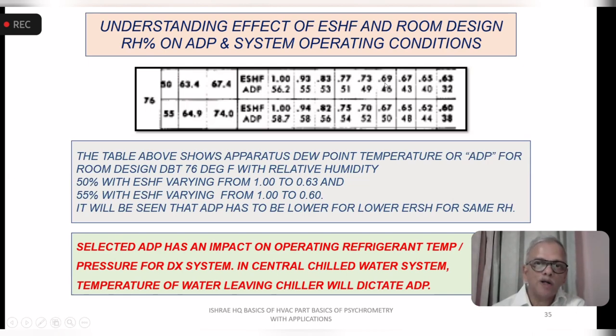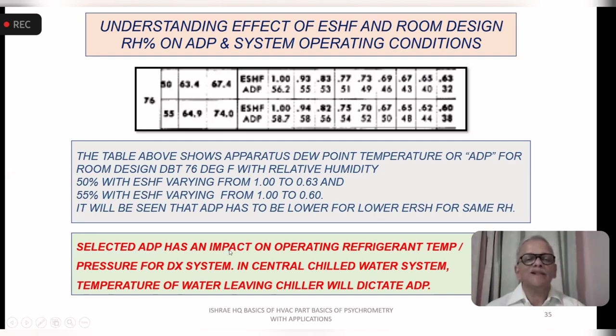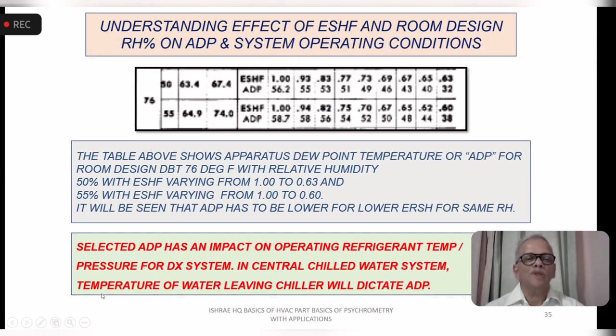So if you have a lower sensible heat factor, it means that the proportion of latent heat, the amount of latent heat to be removed, is substantial, and you have to operate the apparatus at a temperature low enough to ensure the condensation or removal of moisture to the required degree. So the selected ADP has an impact on the operating refrigerant temperature and pressure for a DX system. And in a central chilled water system, the temperature of the water leaving the chiller will dictate the ADP. Now, suppose you have already got a chilled water system where we are talking about 45 and 55, or 44 and 54, depending on the design. These are very commonly used temperatures.